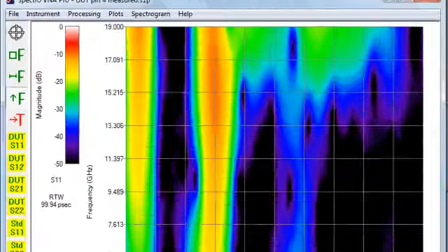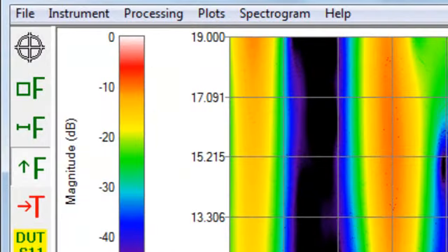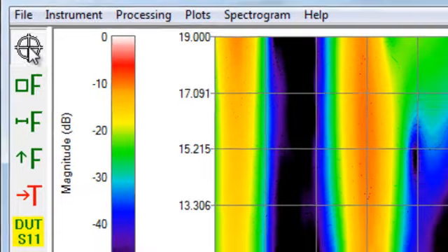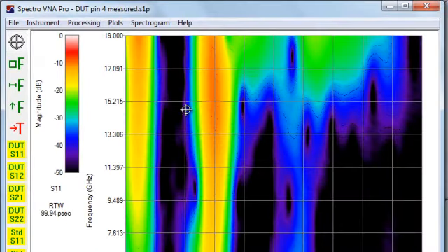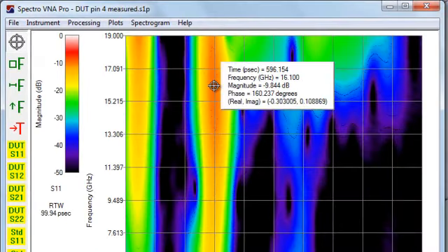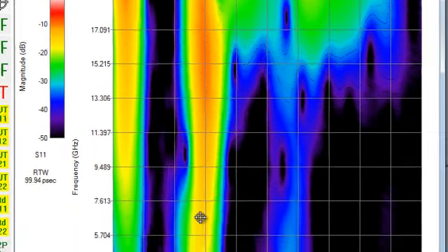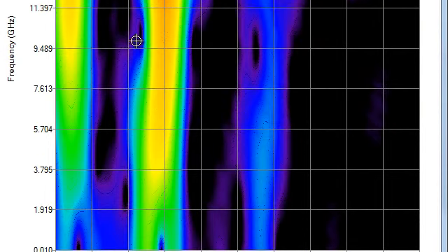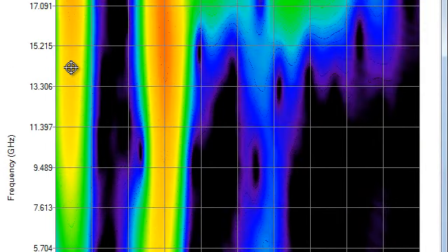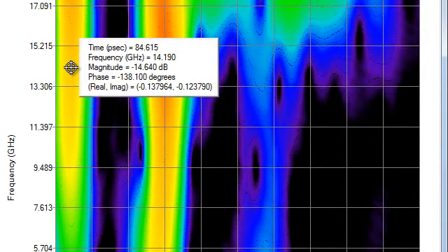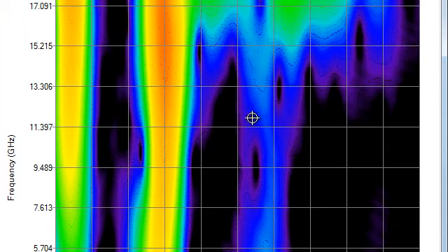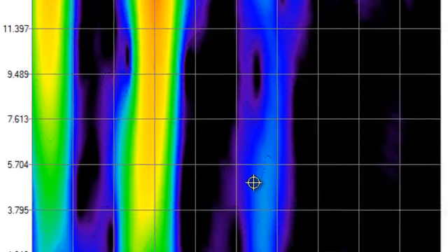We can apply various tools to the display. One of the tools that we can apply is the value tool and we click on the top crosshairs tool and we go on here and we can ask, at any moment in time, at any frequency, what's the magnitude and phase of the S11? Despite the fact that we choose to color this image according to the magnitude, it's a full complex space. Every pixel on here represents magnitude and phase at moments in time at different frequencies.